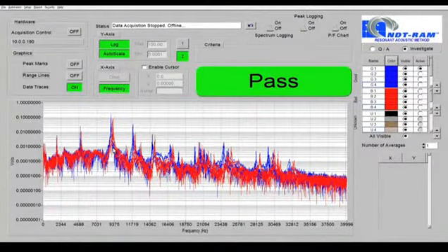Now that the known good parts and bad parts have been tested, it is time to add criteria. When creating criteria, it is important to look for separations in the red peaks and the blue peaks. Turn on the range lines in the graphics section. Zoom into an area where red peaks are separate from blue peaks by holding the control button and clicking the left mouse button.